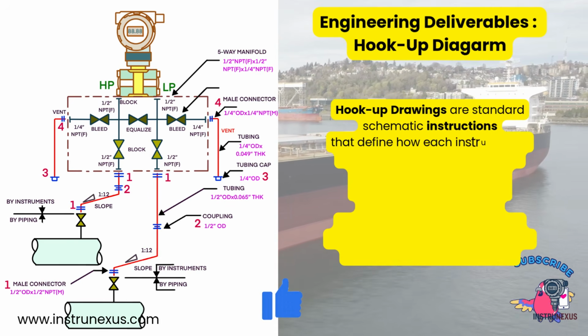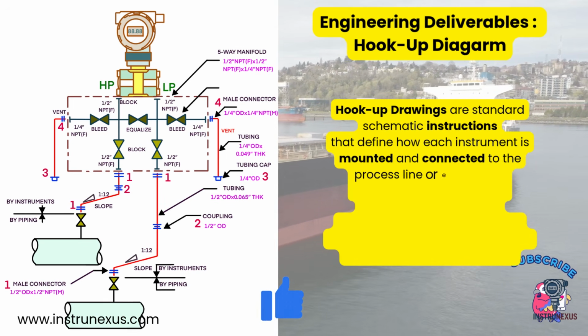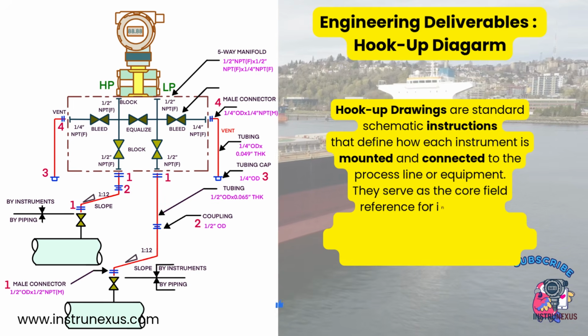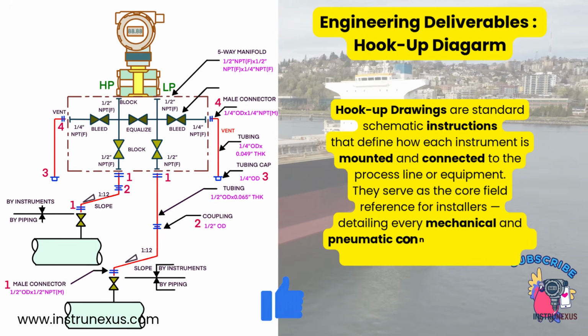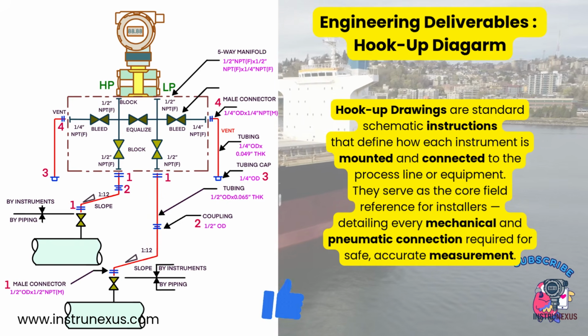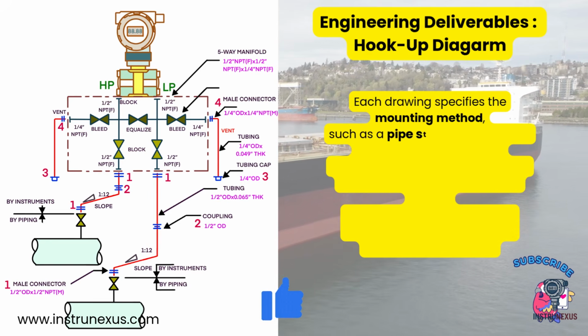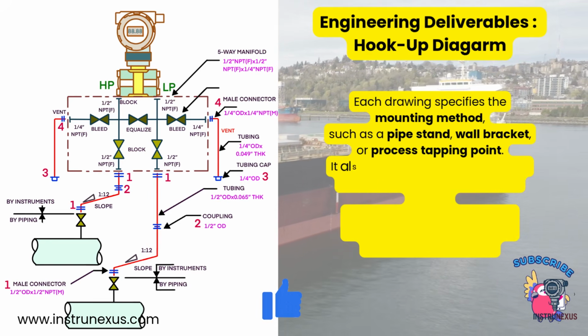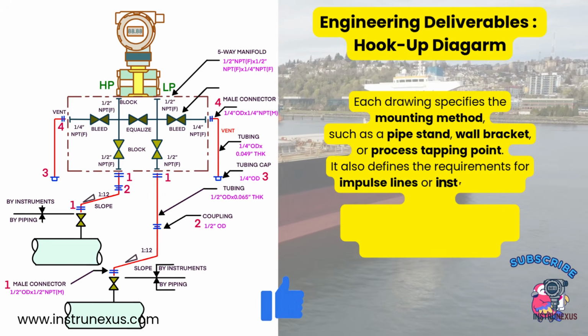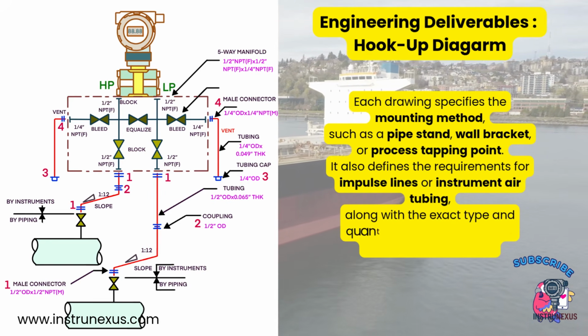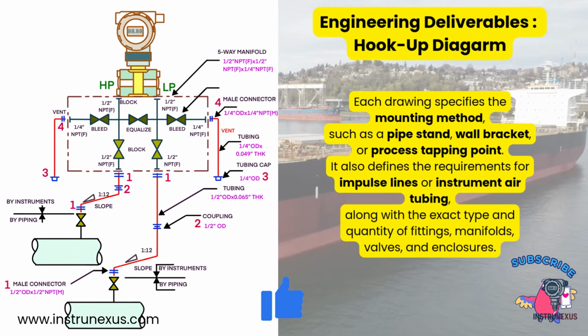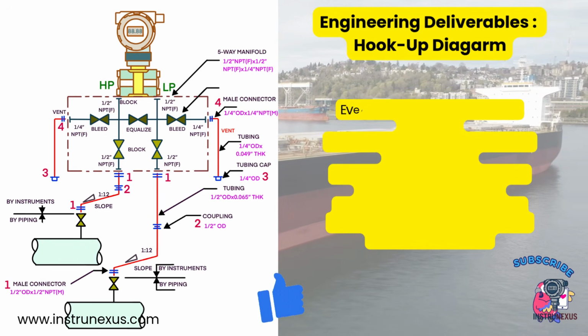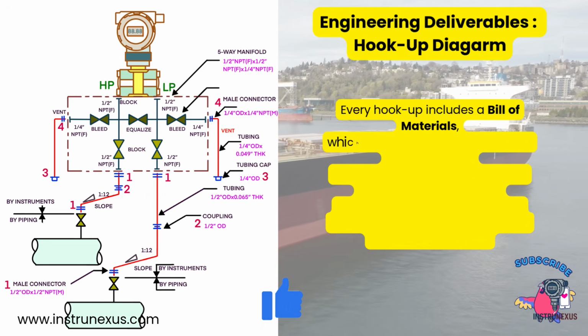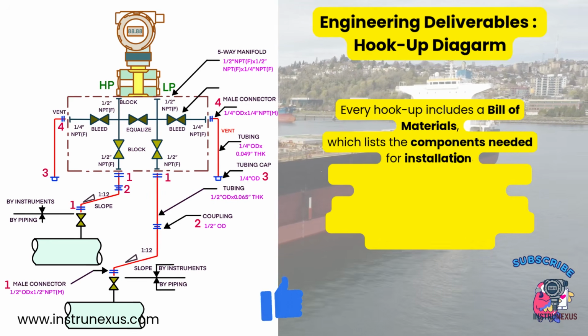Hookup drawings are standard schematic instructions that define how each instrument is mounted and connected to the process line or equipment. They act as the core instruction set for field installers, showing every detail needed for safe, consistent installation. Each drawing specifies the mounting method, such as a pipe stand, wall bracket, or process tapping point. It details the requirements for impulse lines or instrument air tubing, along with the type and quantity of fittings, manifolds, valves, and protective enclosures. Every hookup includes a bill of materials, listing all components required for installation and material takeoff.